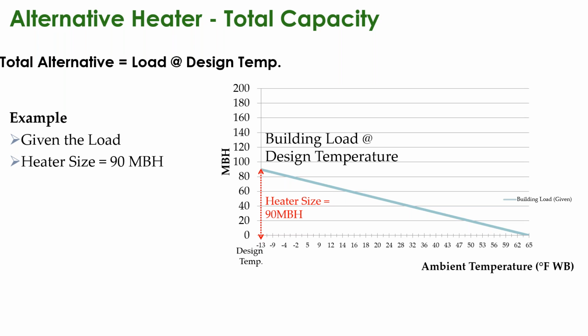when you're using alternative load and design temperature. Now, this happens most commonly, as I said, in areas where it is critical that we have some heat if there's a failure, or I've even had it happen where it is an application where the electrical cost to the building was fixed and they didn't have enough electrical to be running both the variable refrigerant system and the electrical backup. So we figure a point to switch over to full electric because the pressure is dropping to such a point, or the discharge temperature is dropping. It makes more sense to switch over to full electric at that point for the small percentage of time that we're going to be there.